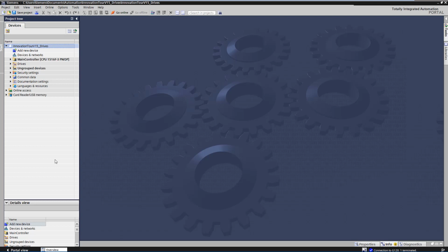This configuration test, which is specified in the drive standard DIN EN 61800-5-2, is intended to detect potential project planning errors and document the correct function, like parameter setting matches the machine. To do this, an intuitive tool is offered in Startdrive that guides you step by step through the acceptance of the safety functions. At the end, you will receive a finished standard compliant documentation, which can be attached to the machine documentation. This means an easy handling and that you save a lot of time.